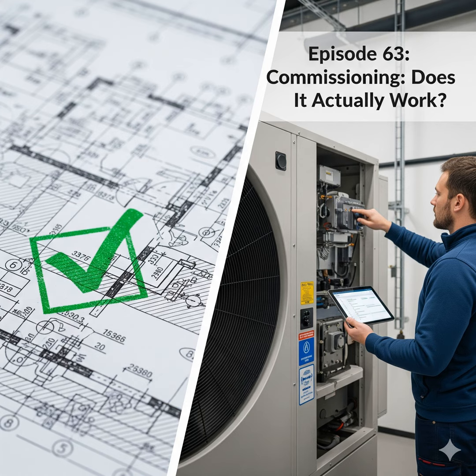Gotcha. How it works, not just if it's there. Precisely. Right. It's about ensuring fire alarms trigger correctly and initiate the proper sequence of events, shutting down air handlers, unlocking necessary doors, not just that they beep when you press the test button. Right, the whole system response.